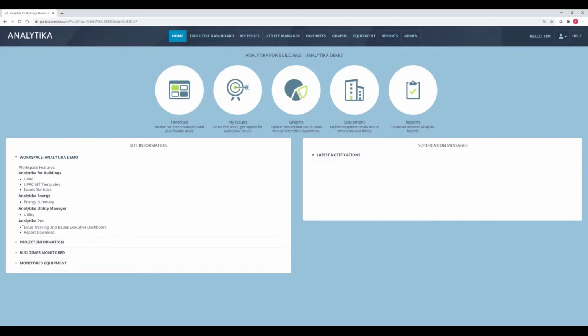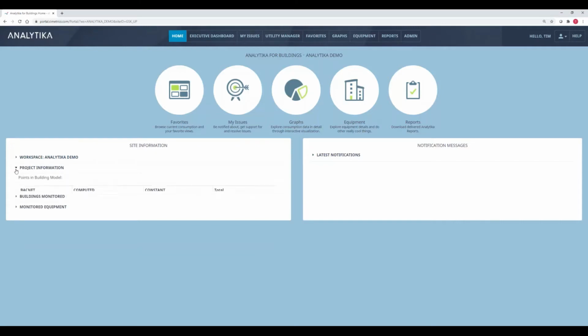These are the different modules of Analytika being used at this site, and the number of points we're polling continuously, 20,000 points from the building automation systems at the campus. We get 4 data samples per hour, ideally, for our analytics. We like to take the present value of every single point once every 15 minutes, for a total of 4 per hour.